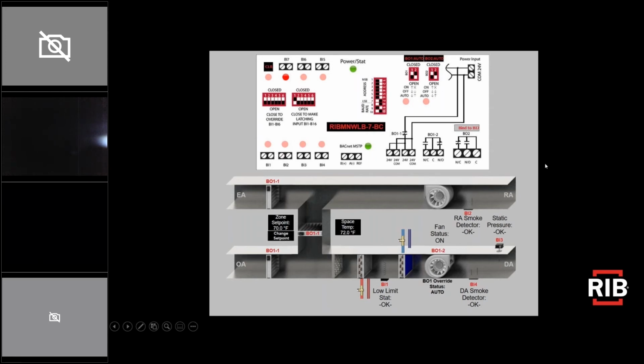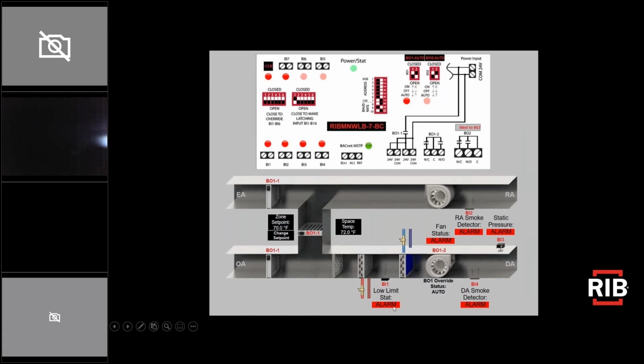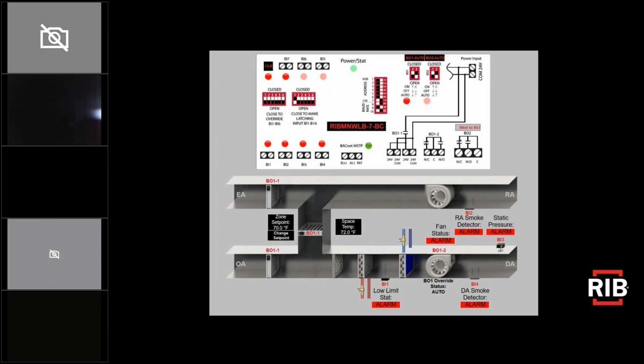Now, if you look at this next graphic, you'll see that things aren't going so well. So if you look, all the sensors have gone into alarm, prompting the air handling unit to shut down. And as you can see from the board, the LED indicators for binary inputs 1 through 4 are on, indicating that those devices are in alarm state. Now, normally, once these sensors go back into a good state, the relay would automatically turn back on to power your loads. However, with binary input 1 being latched, the load will not turn back on. So in this example, you would have to push the onboard test button or clear the latch over the network in order to return to a normal state. And next slide, please.